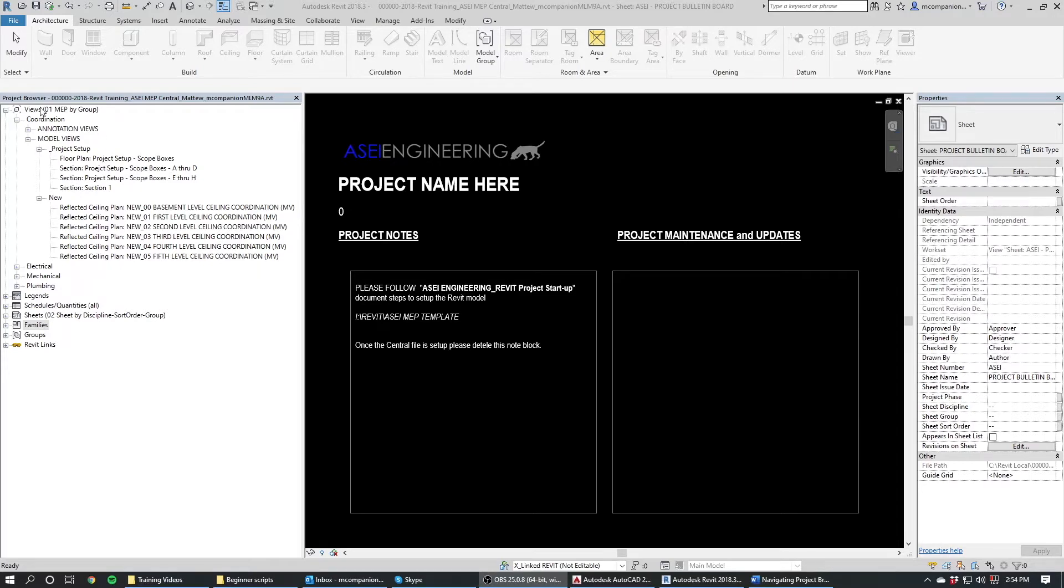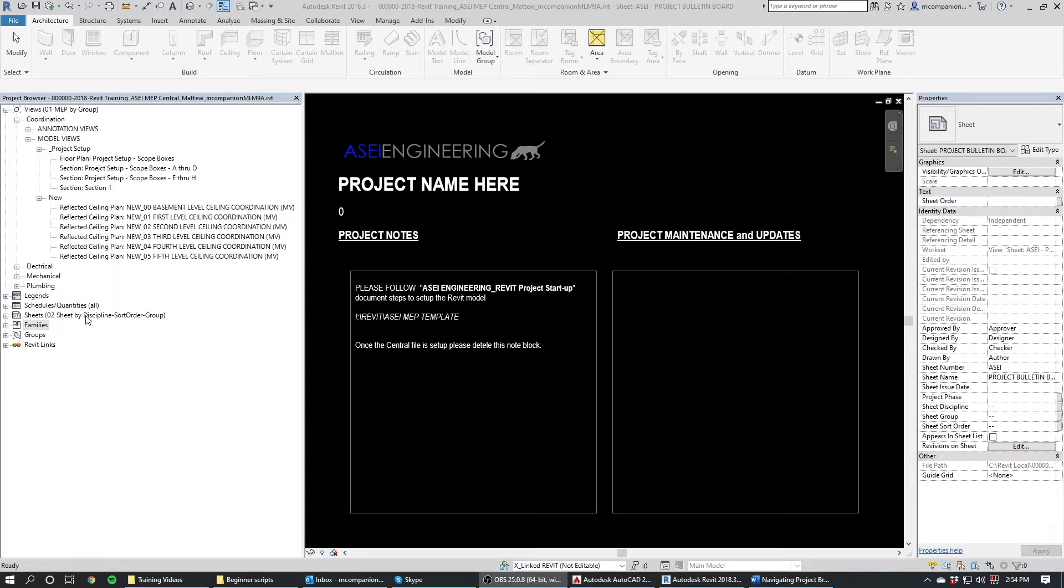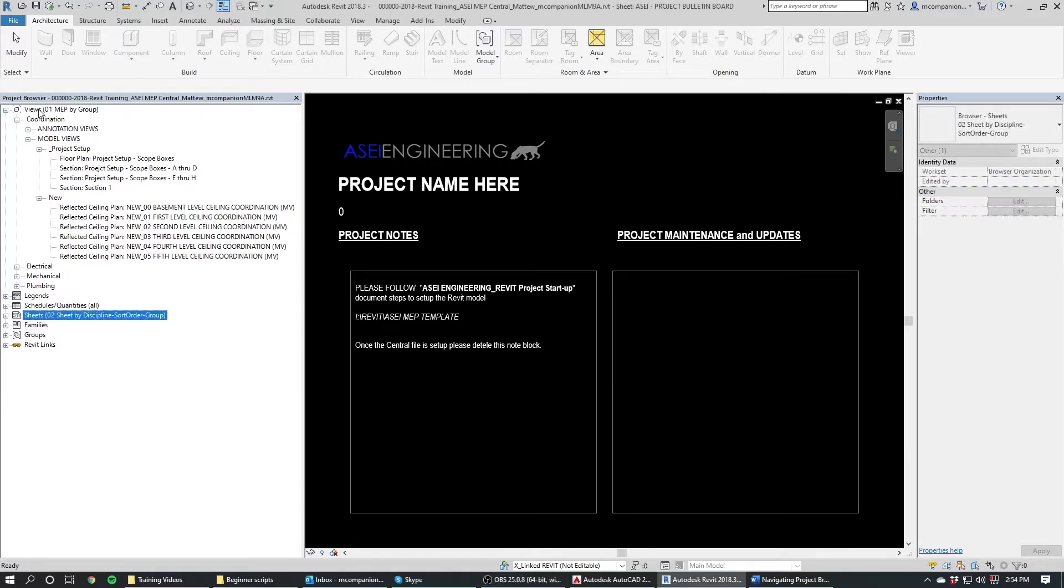So starting at the top up here we've got views. Now views are basically the AutoCAD equivalent of model space. So your view is where you do all of the work and where you put all of your notes and your key notes and all of that. The sheet down here, your sheets are what your title block is on and you put the view, you drag the view onto the sheet and then print the sheet. So the sheet has your general notes and your keyed notes. The actual text file for keyed notes is on the sheet and then the little family with the circle and the number would be on the view. So that's basically the difference between views and sheets in Revit.